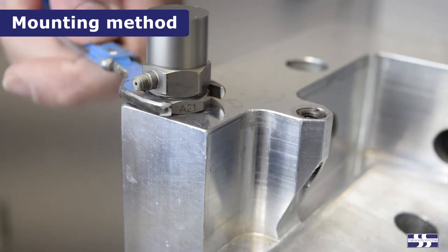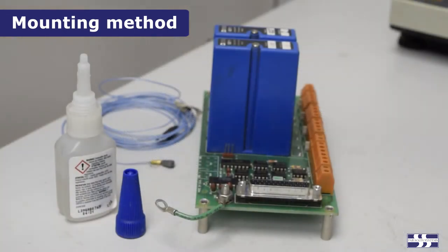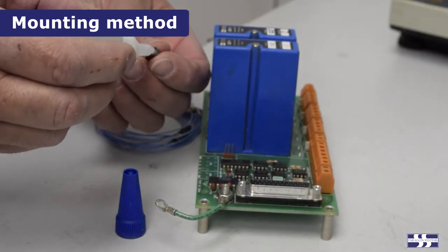High strength adhesives can achieve similar performance as a threaded stud, and are the preferred attachment methods for very small accelerometers which do not have a stud mounting.